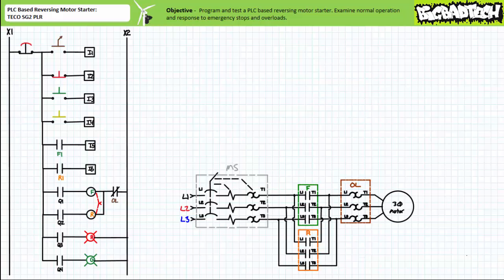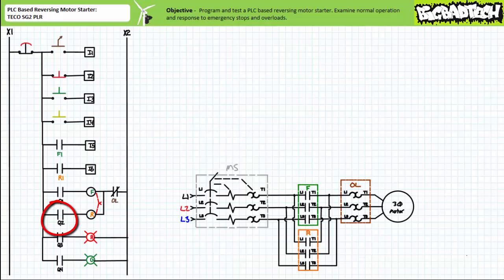Let's now examine the field output devices. Electromechanical relay output Q1 directs the operation of the F-contactor coil, hardwired with a normally closed overload contact. Electromechanical relay output Q2 directs the operation of the R-contactor coil, also hardwired with the same normally closed overload contact. This hardwired connection between the two contactor coils and the normally closed overload contacts allows the overload to have the last say as to whether the motor is energized, and never surrenders complete authority to the PLC. Wired in this fashion, the normally closed overload directly de-energizes either contactor coil in the event of an overload without any programmed instructions.